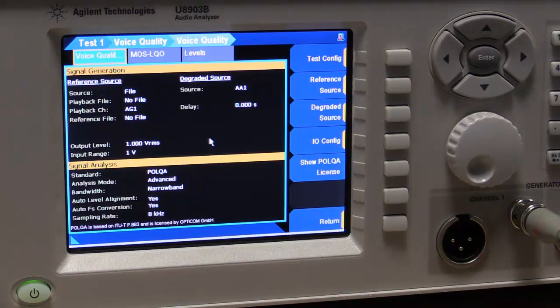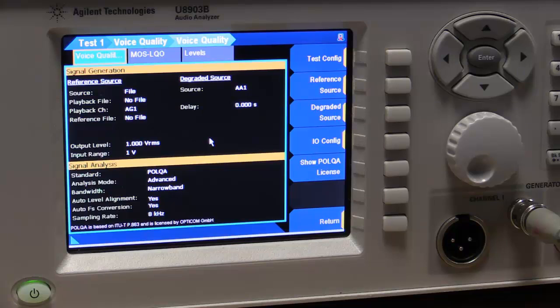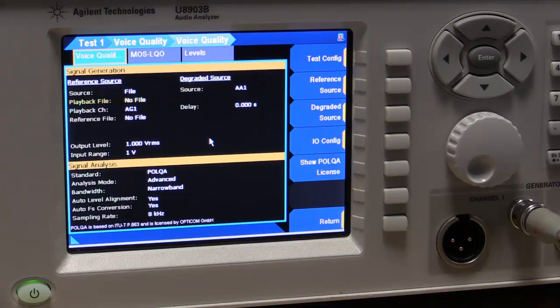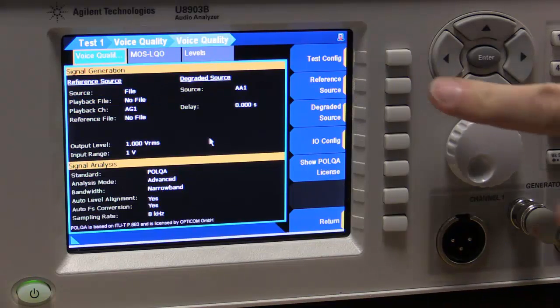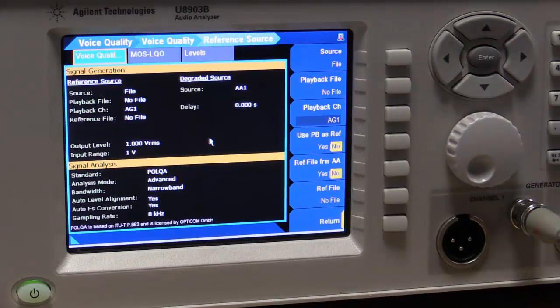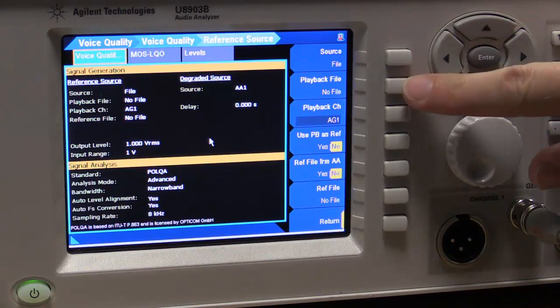The next thing we need to do is we need to tell the instrument what the reference is. So we need to give it a reference file to play through the system. It will then record that and do a comparison with what comes back. We've already got a file inside the instrument. So our source here is going to be a file.